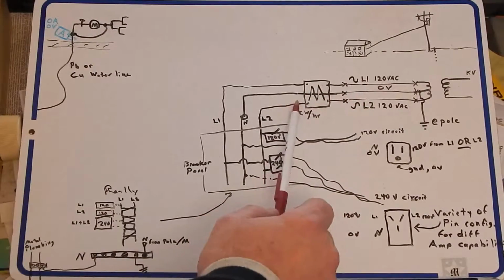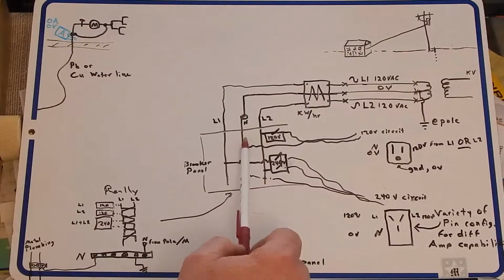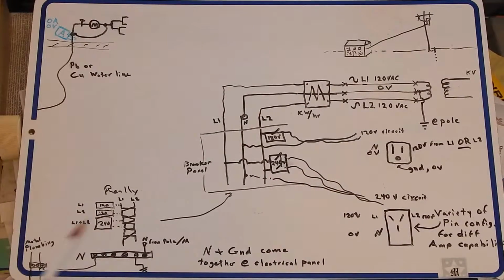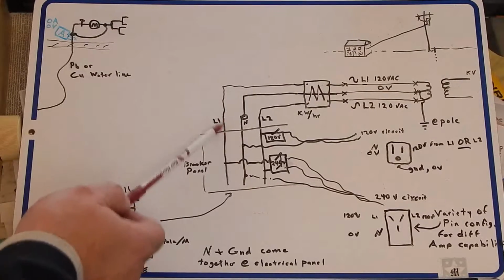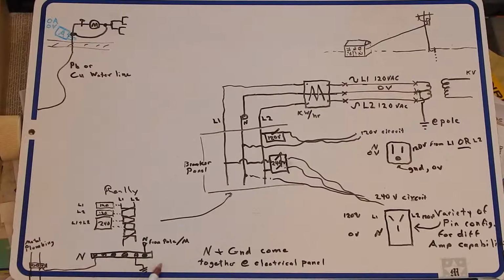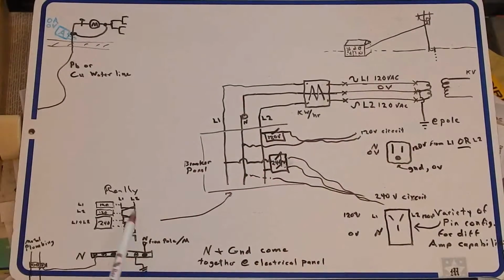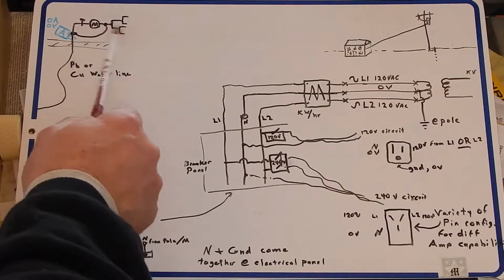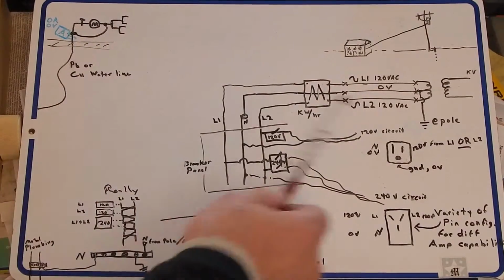So it'll pass through the meter. I don't think the old meters needed a neutral connection, but the new ones probably do, the electronic ones. At any rate, it goes into rails in the box. In reality, the neutral is on a bus bar in the box, and all these white wires will be going to here for neutral. And your grounds. Your ground to the earth should go to a ground rod. Your ground from the pole, which is this wire here, this neutral. And also, if you've got metallic plumbing in your house, there should be a ground wire to your plumbing. And that's how it gets back to your meter, your water meter, in a case of a failure of this neutral.